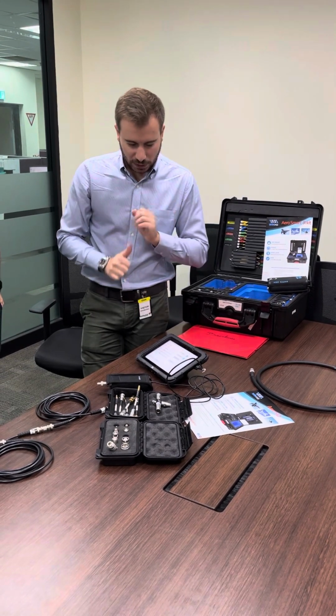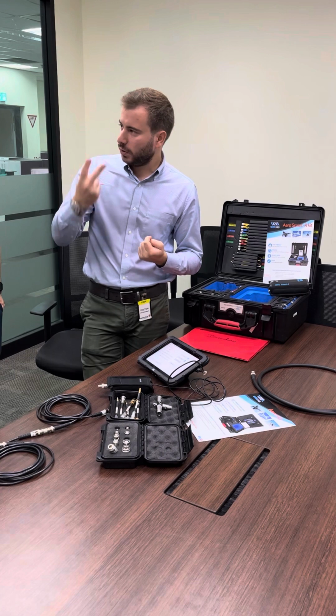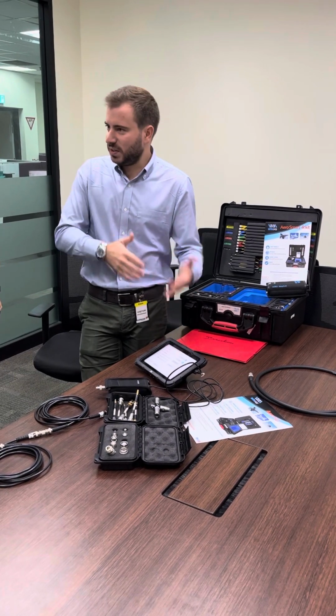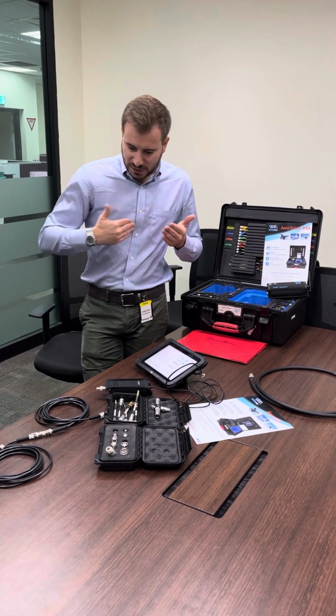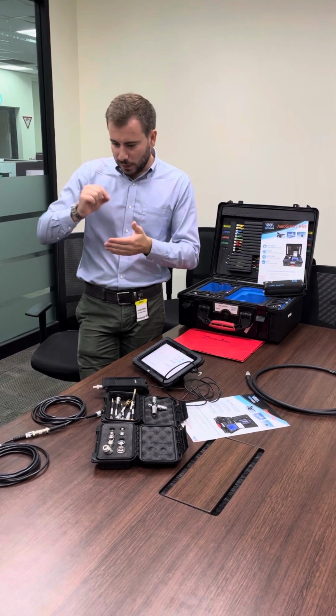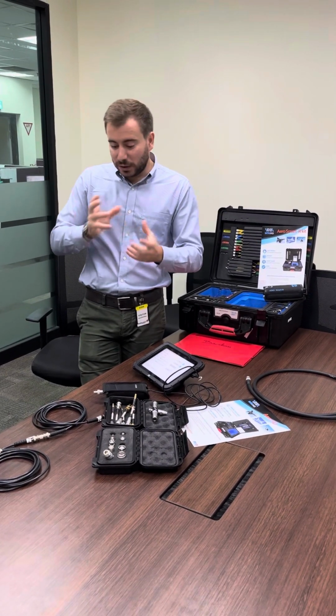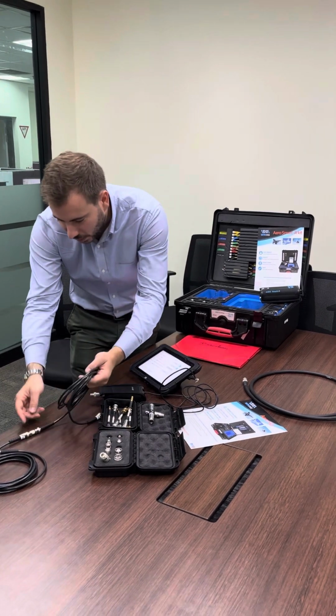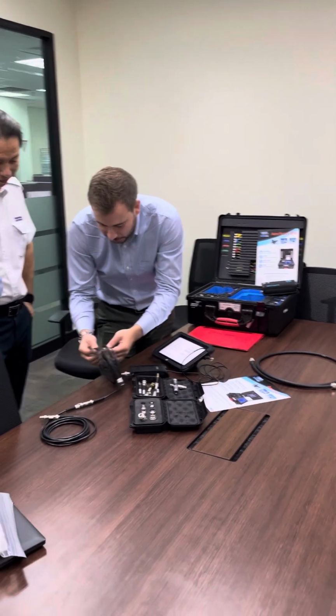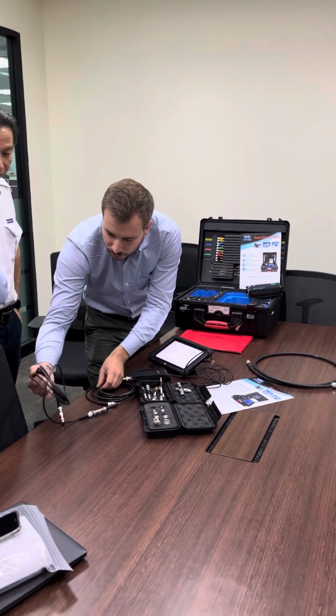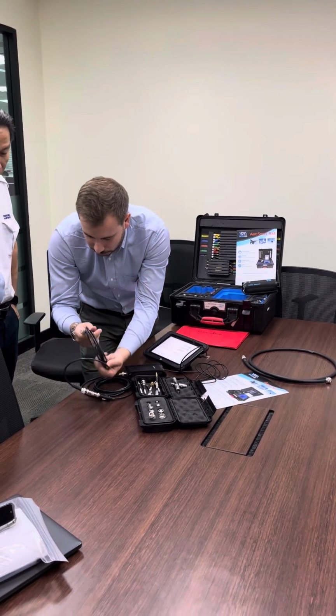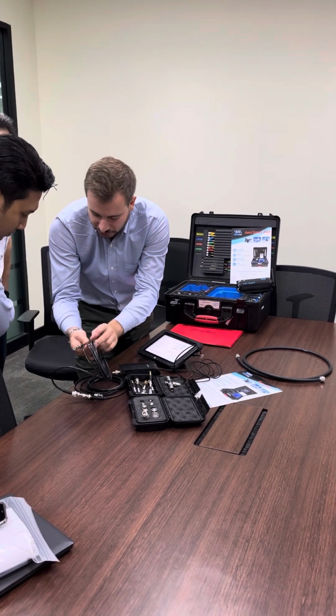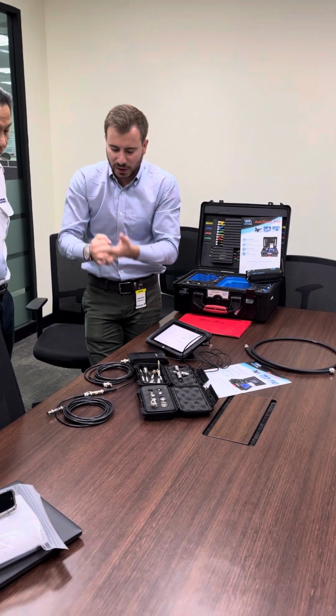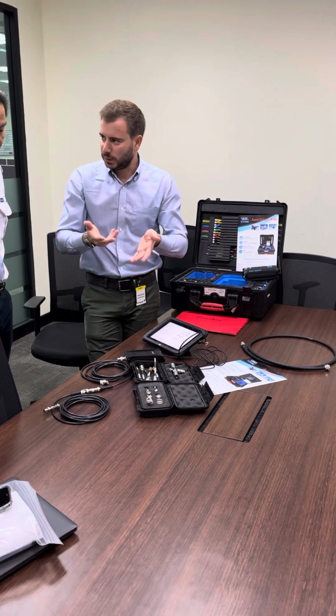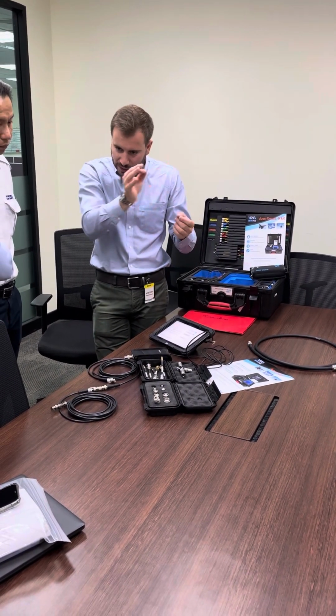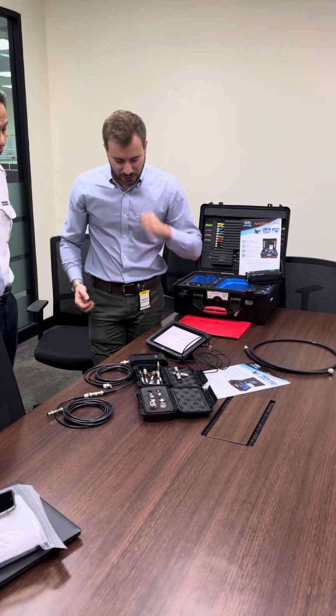That's the first check. Then we can do a second test, called DTF, distance to fault, in order to see all the little spikes which can correspond to a fault, maybe. It could be a shield fault, it could be an insulation fault, it could be a tie wrap too tight, it could be a bad connector, many things. So we will be able to see and locate accurately with the distance to fault.